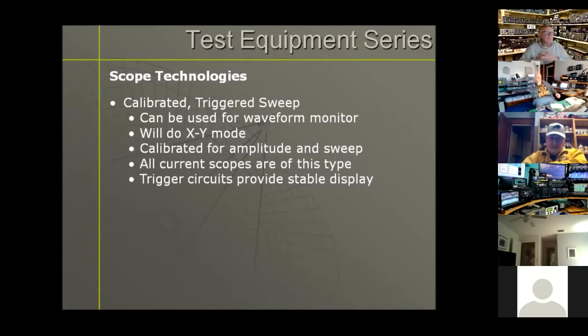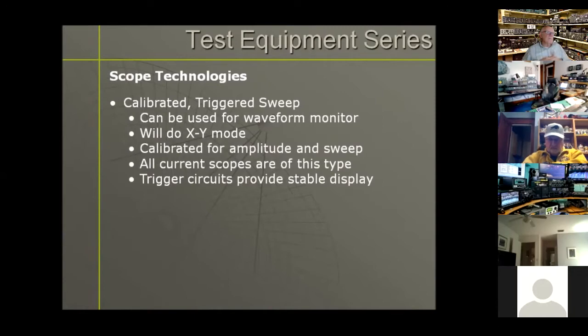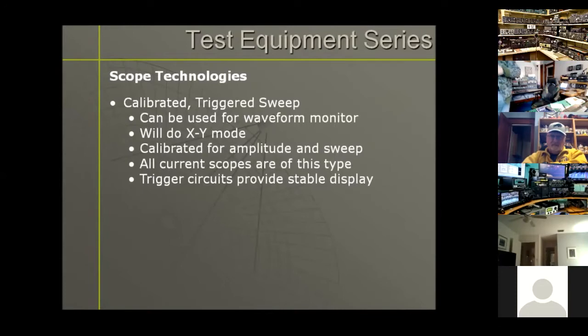Continuing with scope technologies: calibrated and triggered sweep scopes can be used as waveform monitors, used in XY mode, and are calibrated for amplitude and sweep so you can actually measure voltage and time, and inversely measure frequency. All current scopes are of this type — triggered sweep, calibrated for voltage and amplitude so you can measure voltage accurately, and calibrated for sweep times so you can get exact delay times, period times, and the inverse frequency of the signals you're looking at.